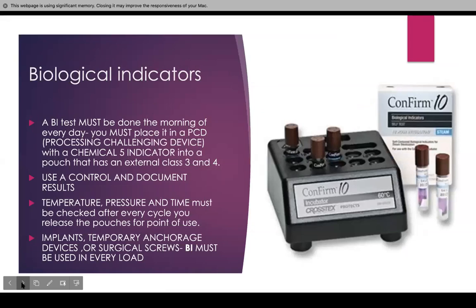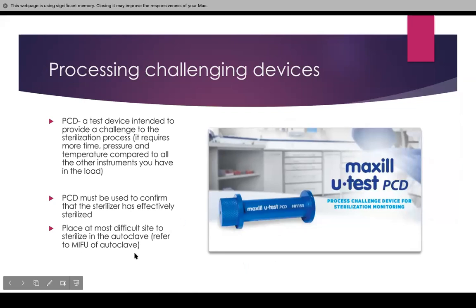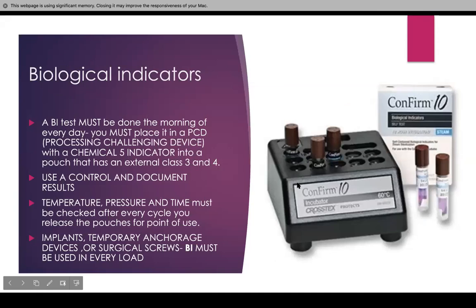Biological indicators are these little tubes — these are just pictures to give an example, it's not the exact same brand but something similar. They always come in tubes and they test spores — they test if anything is growing within the autoclave. A BI test must be done the morning of every day. This is the processing challenging device. We are going to place the BI in it and then place a class 5 chemical indicator.